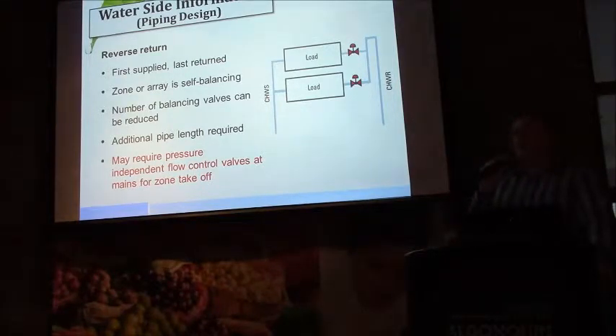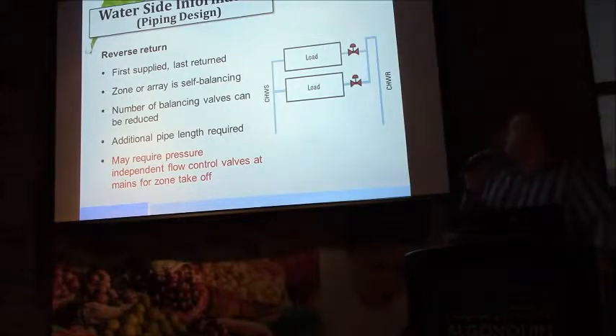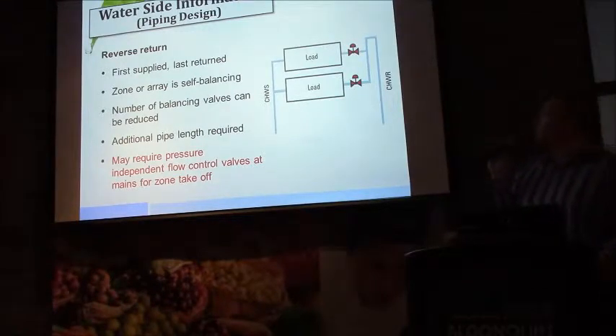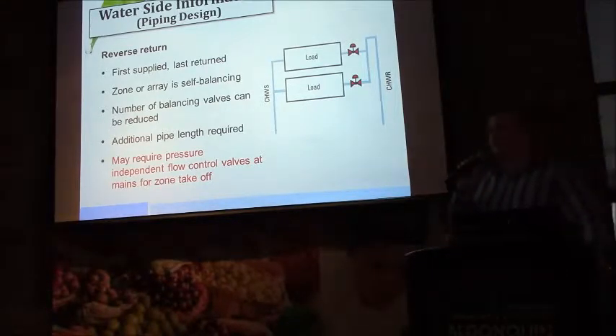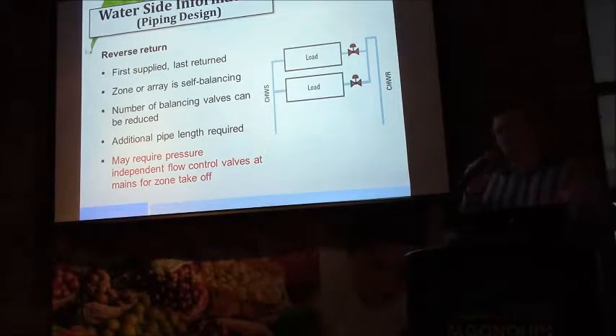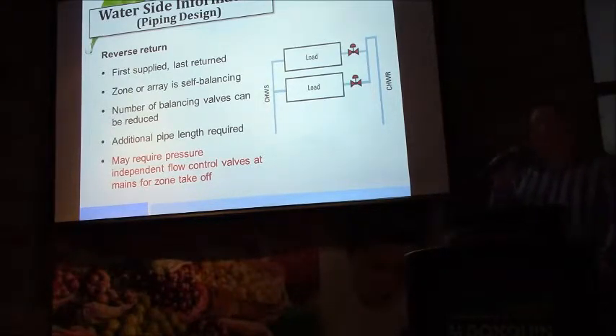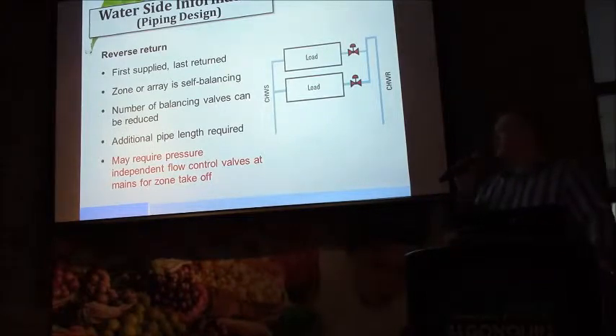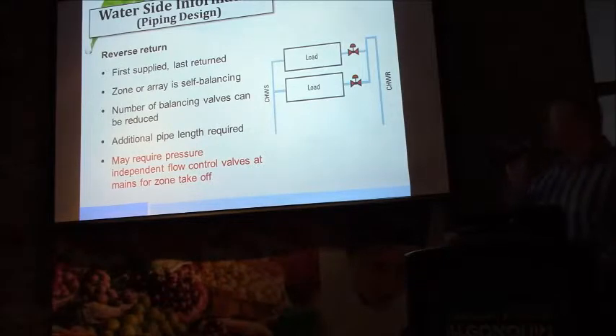For comfort, if we decided to consider a beam for a four-pipe application in the core, that can create a veritable nightmare in terms of labor to hang all that pipe, although that's an available option to you as a designer. In this particular instance, we're showing a control valve that could be on each connected beam, but for a system that is piped with reverse return, conceivably we could solve that solution with one control valve for the zone, assuming all the beams that are in that space are the same length, and with a low-cost ATC valve, we could energize that zone as necessary, and that beam array would flow the adequate GPM that we require for stable capacity or stable operation.